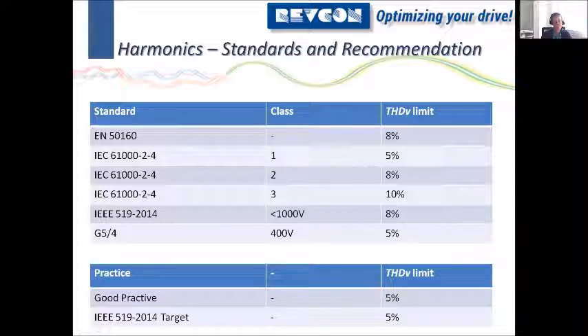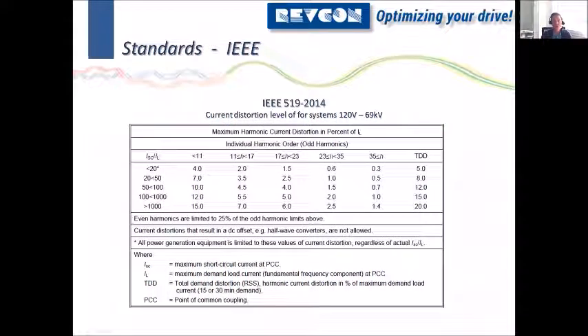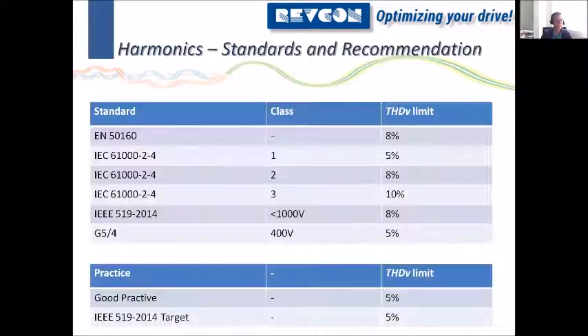But if we look at the tables used inside the IEEE, we can switch to the next page. They give you some recommendation on currents that you should have when you make an installation. So let's make an example. If we have an installation with a short circuit current ratio of 20 to 50, they tell you to have a total demand distortion, a current distortion, of less than 8%, including all the individual values. If we follow this standard and this recommendation, we will not get to the limit of 8%. We will get far below 5%. So actually, that's why I mentioned it differently. The limit of the IEEE 519 is 8%, but they practice or they target a 5% limit.